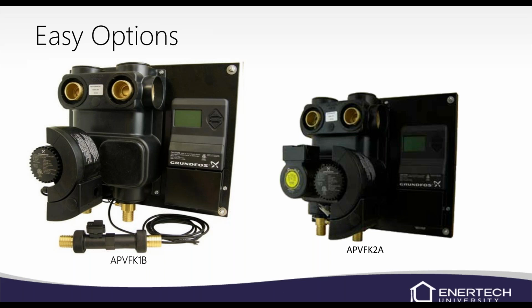If you ever do run into a situation where it loses the screen, we do recommend this: we get some dirty power sometimes from the unit on the low voltage side. So if that controller fails, we're going to send you a wall transformer so you can get your power off the wall and not the unit itself. Just keep that in mind if you ever have someone who's got a problem with the controller and they're not using a wall transformer. Let us know, and we'll get one from GeoFlow sent out to you under warranty.